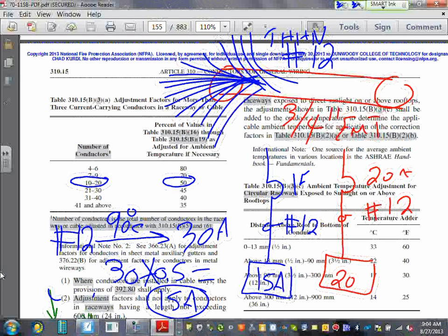So you went from number 12 pulling 20 amps, if it's only three hots in a conduit, to the same number 12, if you group it with a bunch of other offenders like it, carrying no more than 15 amps. So what do you do? You put a 15 amp circuit breaker there instead of a 20. You feed only 15 amps worth of lights or receptacles out of it. Only 15 amps. Any comments, guys? Any questions? Do you see what derating based on temperatures and bundling is all about?